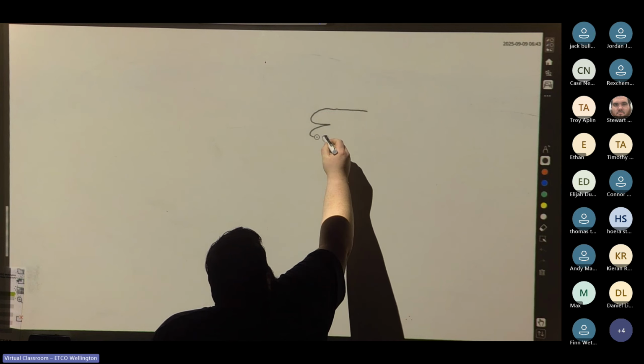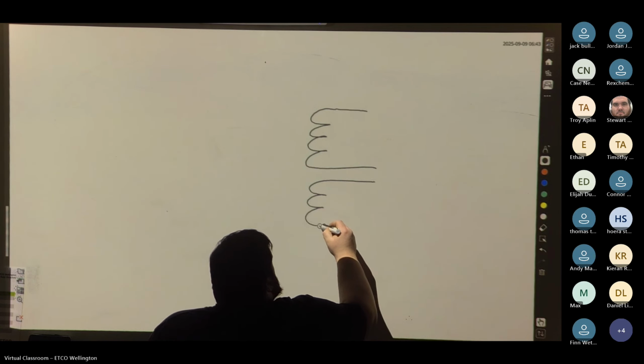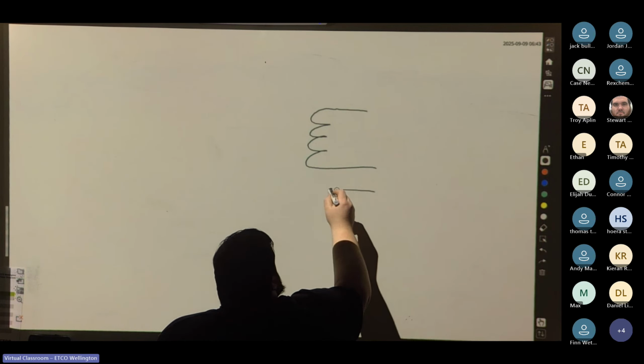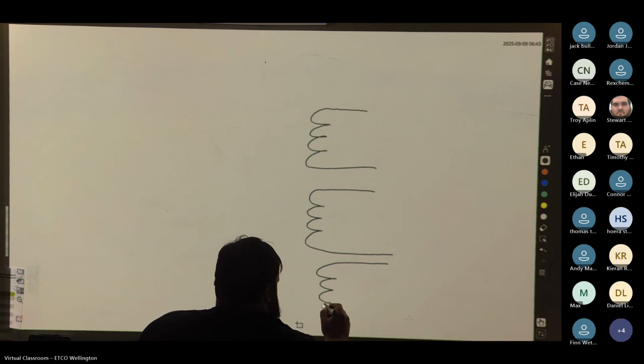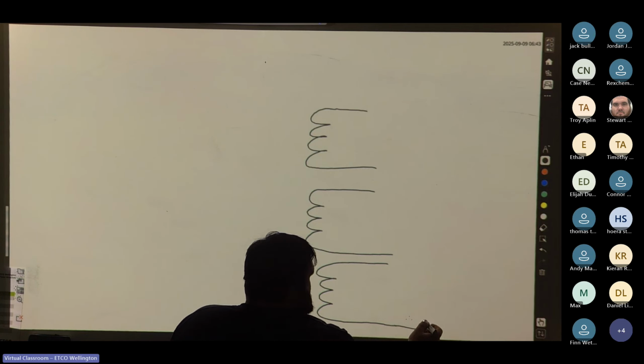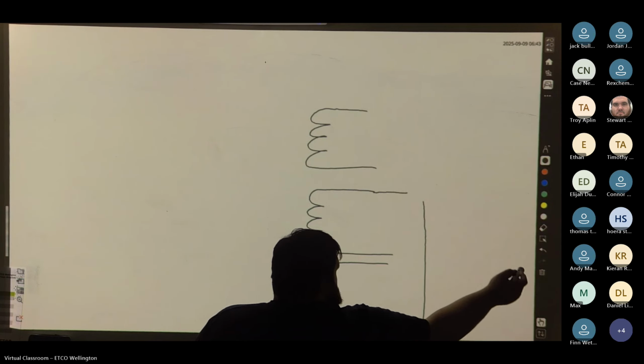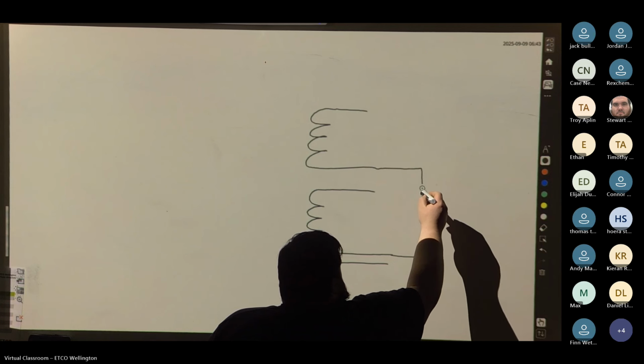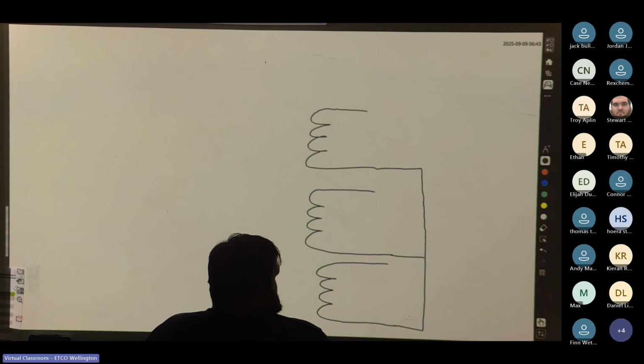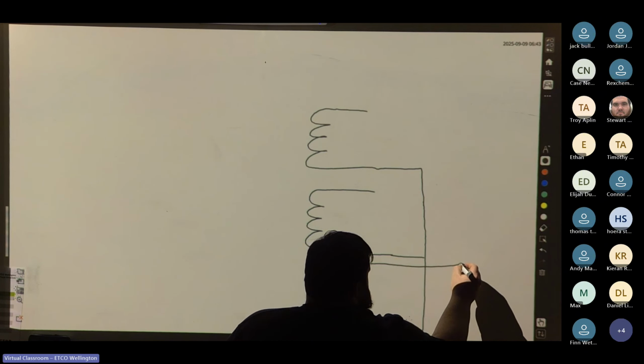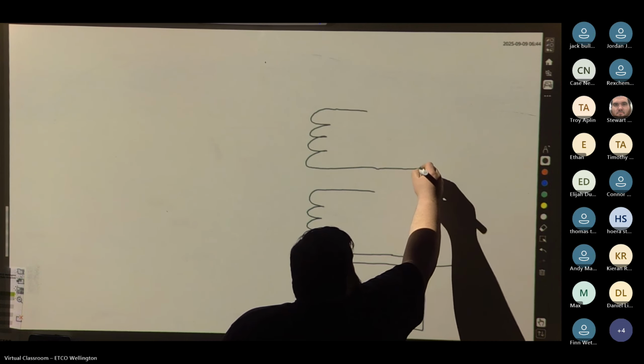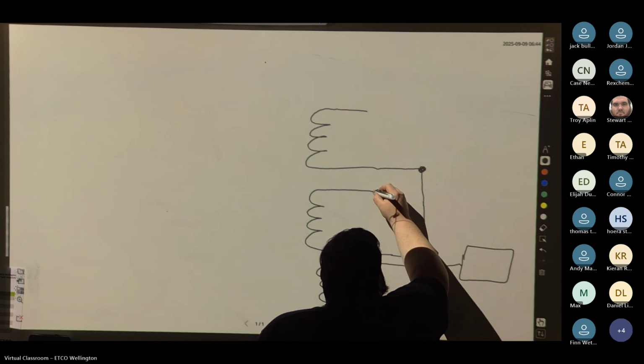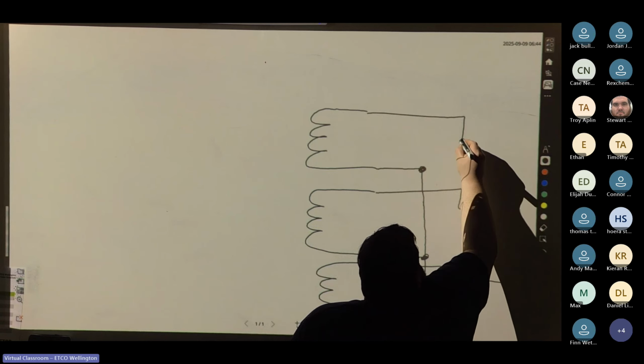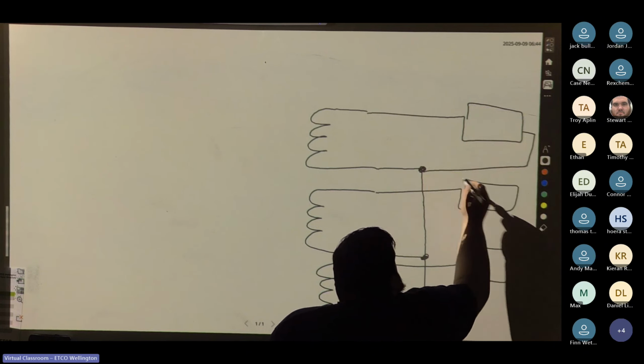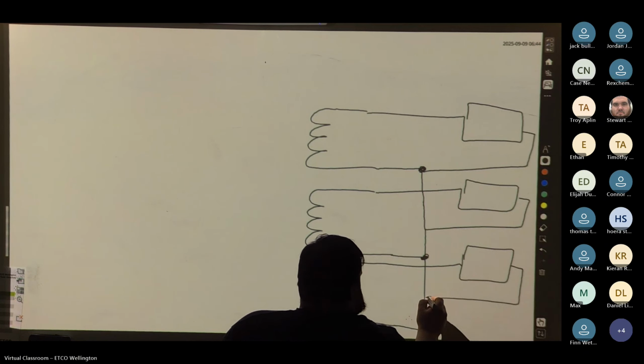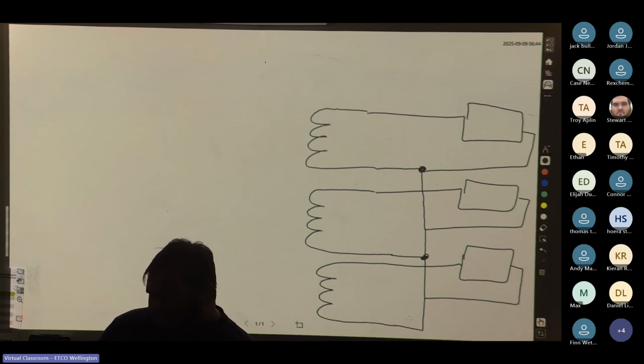If we look at an actual transformer, we'll just do the one side. We've got our windings, 1, 2, 3, 4. What we would do is take the second of each winding and connect them together. And these would be connected to our loads: this would be a load, this would be a load, this would be a load, and then these would all connect back to the neutral line. So we've connected each side of the transformers together.